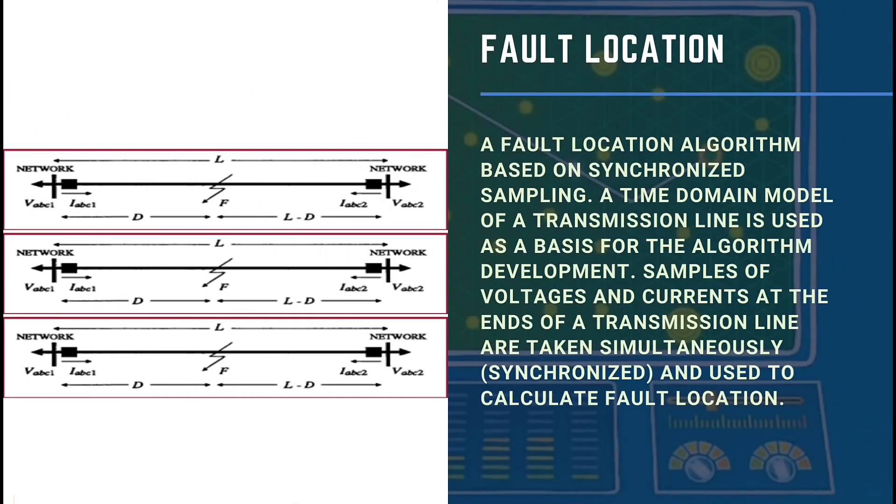Fault location: A fault location algorithm based on synchronized sampling uses a time domain model of a transmission line as a basis for the algorithm development. Samples of voltages and currents at the ends of a transmission line are taken simultaneously, synchronized, and used to calculate fault location. Phasor measurement units are installed at both ends of the transmission line, measuring the three-phase voltages and three-phase currents simultaneously.